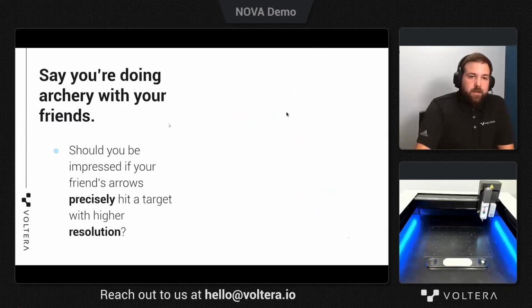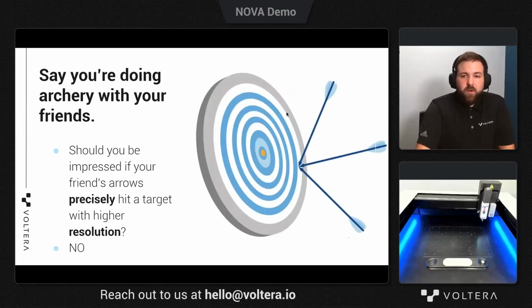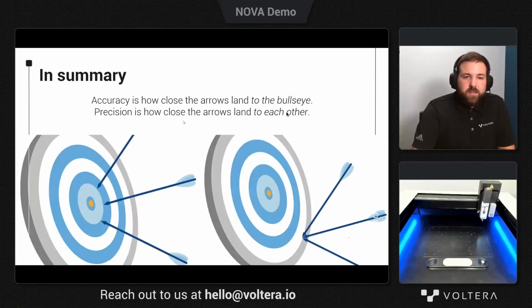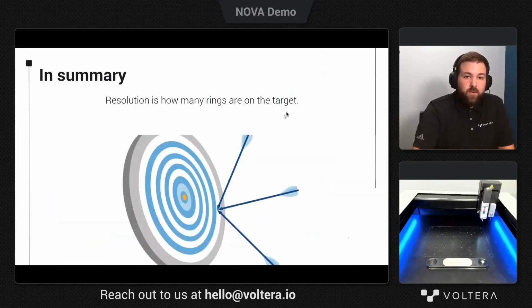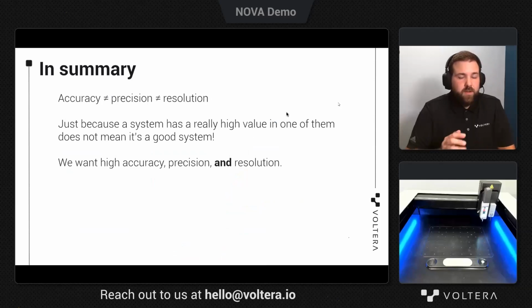Now, should you be impressed if your friend's arrows precisely hit a target with a higher resolution? I mean, no. If there's more rings on the target, it just means we have more defined area of where the bullseye might be. So in summary, accuracy is how close the arrows land to the bullseye, whereas precision is how close the arrows land to each other in repetition. And the resolution is how many rings are on the target. So accuracy doesn't equal precision, and it doesn't equal resolution.